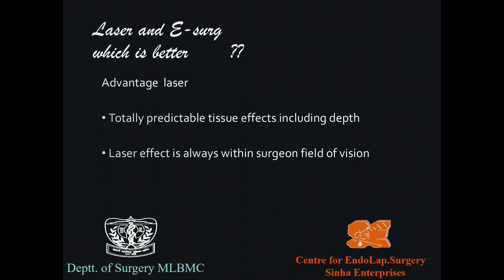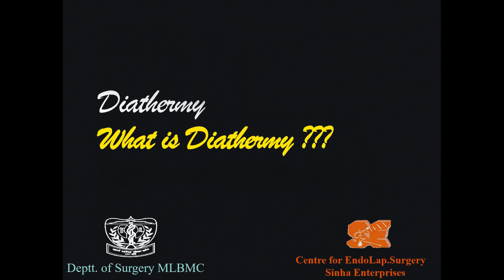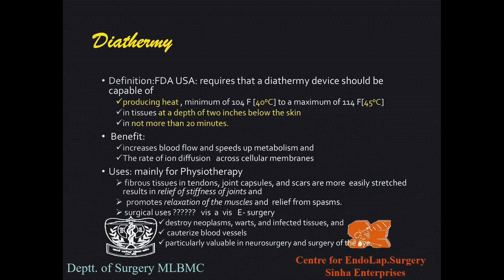A commonly misused term: in the OT staff say 'bring on the diathermy' meaning the electrosurgical unit — but that is wrong. Diathermy is defined by the US FDA as a device which produces heat between 40–45°C at a depth of two inches below the skin in not more than 20 minutes. Compare this with an electrosurgical unit which reaches up to 400°C. The benefit of diathermy is it increases blood flow and speeds metabolism and rate of ion diffusion across the membrane — it is stimulatory to healing.